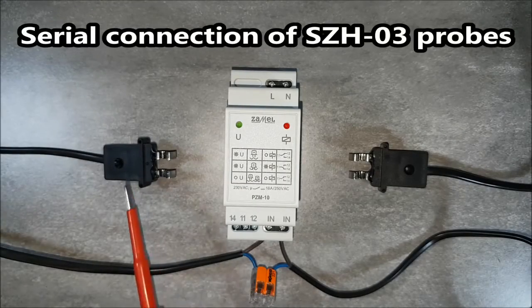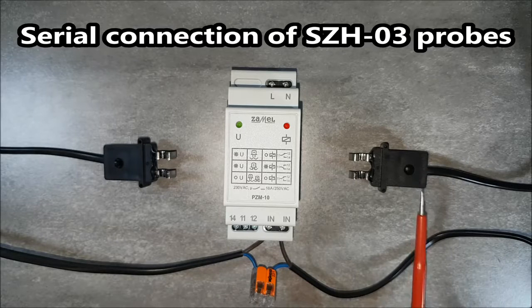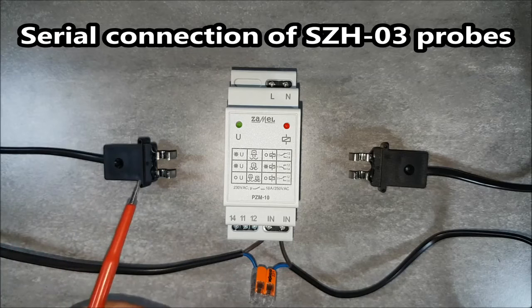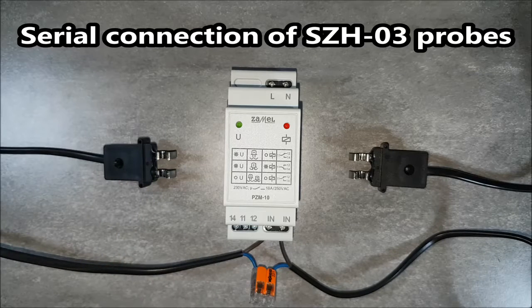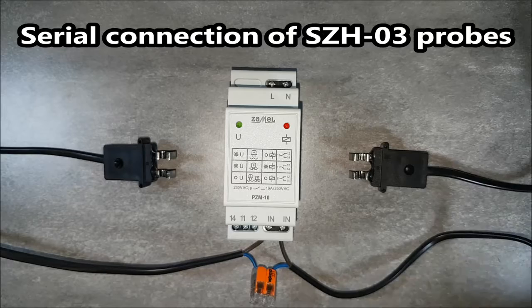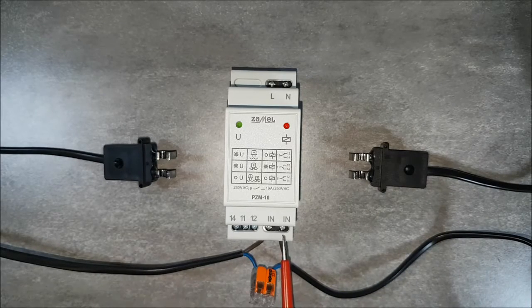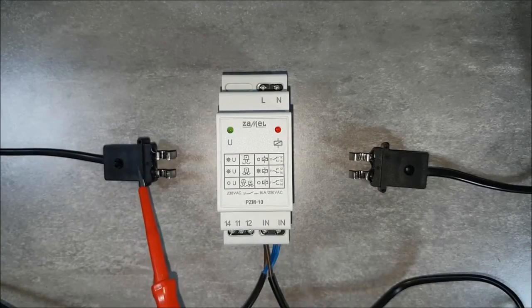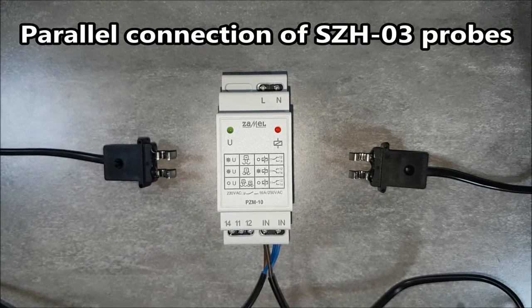The flood probes can be connected in serial or in parallel. Serial connection of the probes causes the relay to operate when all probes are flooded at the same time. Parallel connection causes the relay to operate if any flooding probe is flooded.